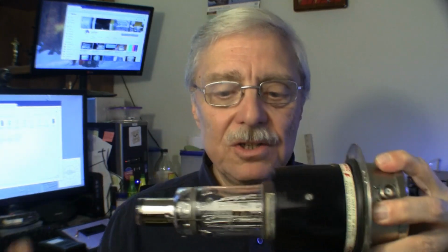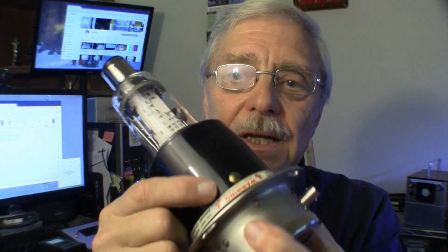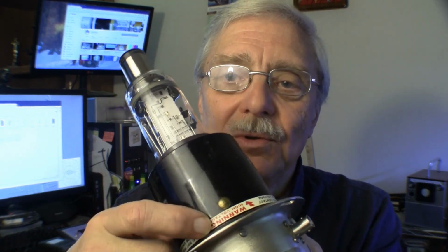But you do have to watch out for something - if this is not in its shield, there are some contact buttons here that are clearly labeled high voltage. So when operating it, make sure you have plastic insulation, some form of insulation here. This body is made of Bakelite, which I think is because it'll withstand the cryogenic temperatures they run these at - you run a photomultiplier tube very cold to lower noise.